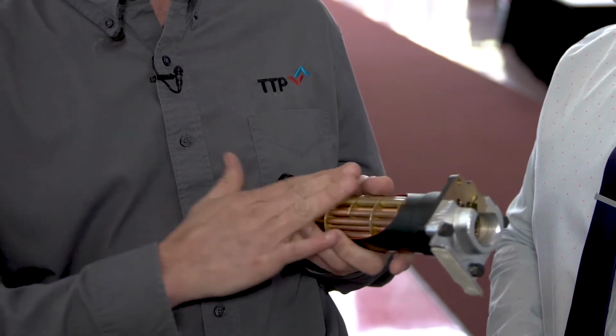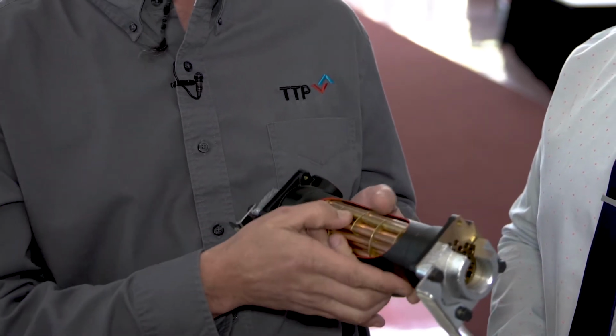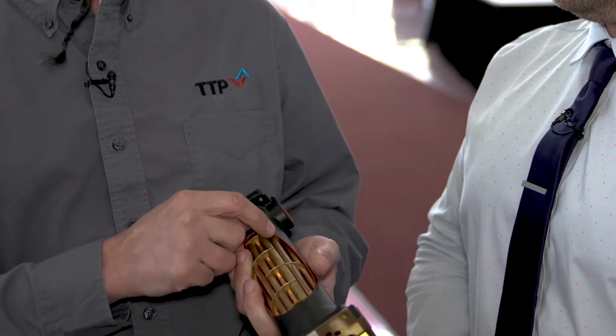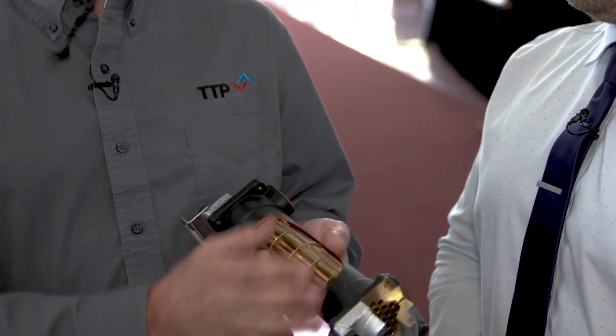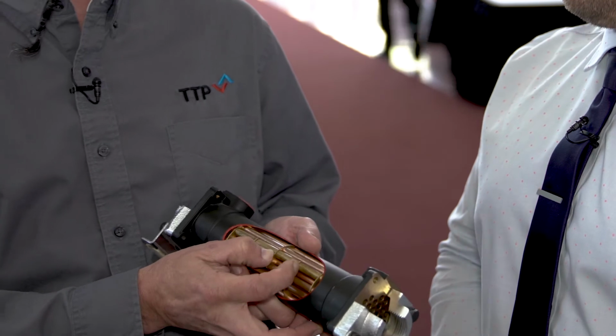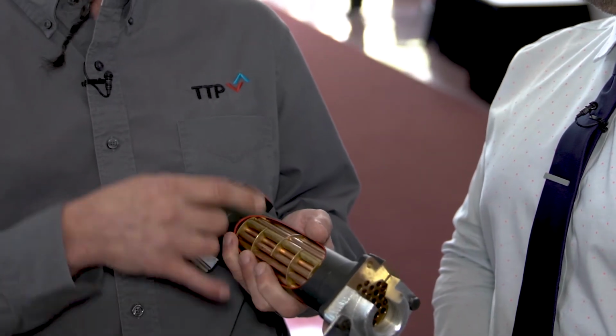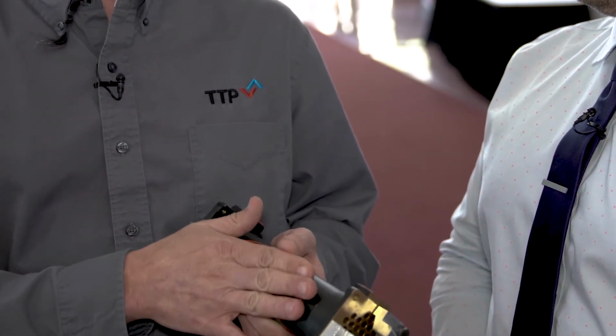Match the velocity profile on the shell side of the heat exchanger, which is typically the oil side. So we've got two choices. One is to figure out what the flow rate is going through the heat exchanger, possibly motor displacement times RPM, or pump displacement times motor RPM, would give you the flow rate. The other way is to physically figure out what your baffle spacing is, which is what we're trying to do here. You could do this by taking an angle grinder and cutting yourself a little window in the side of the heat exchanger so that you can actually measure this distance. That is the exact baffle spacing that you want to use to keep that velocity profile in that heat exchanger.